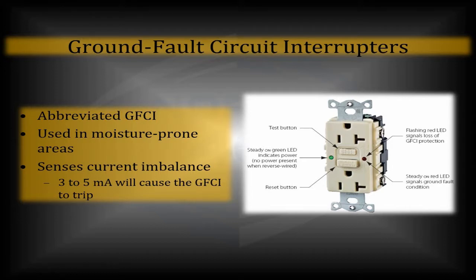The one thing to keep in mind with GFCIs is that the way they work is very interesting. There's a reason they want them in wet locations. It doesn't just trip on a short. That's not what we're looking at here. It trips based on the amount of amperage going out and the amount of amperage coming back. You could picture it as a hot and a neutral wire. If the amount of amperage going out and coming back is different, and the difference equals 3 to 5 milliamps at least, then the GFCI is going to trip.